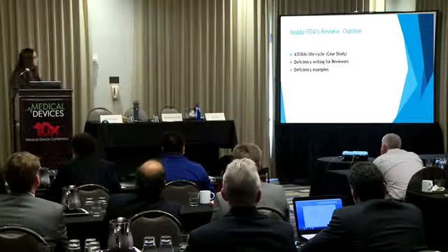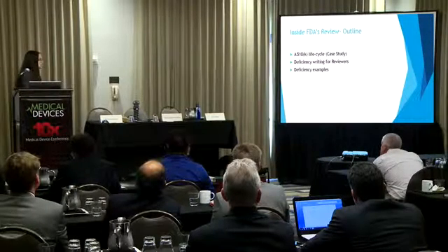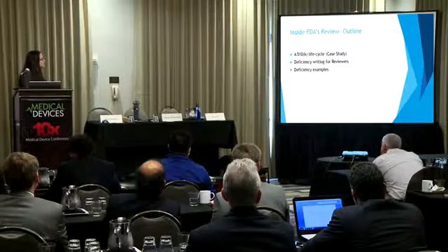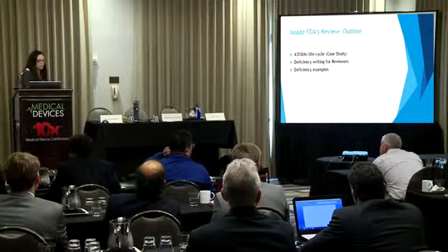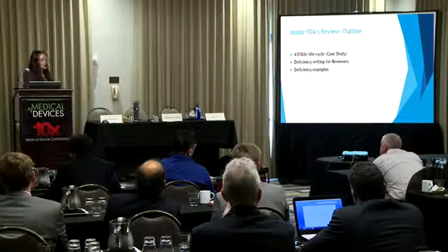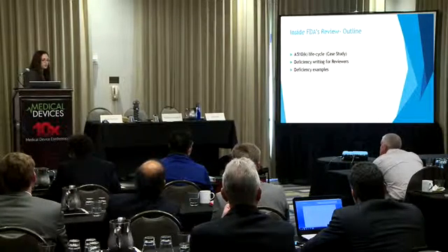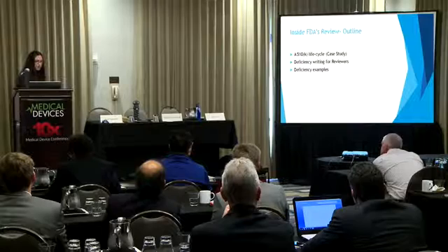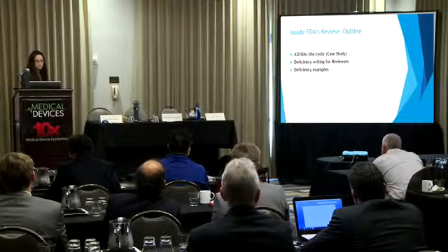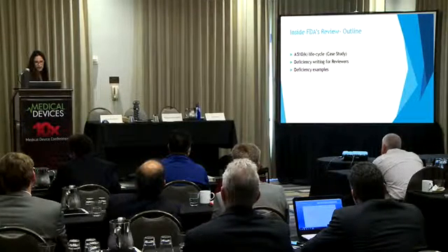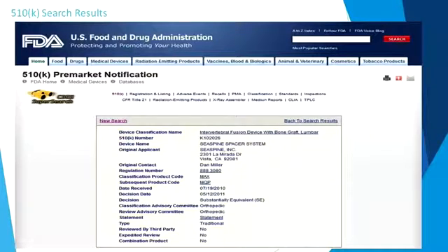So Rob had a great slide with the database. So this is the 510K database. I looked up this is for a client that was looking for something that had a nano coating. That was something they wanted. They had a nano metal coating and they wanted a predicate. So this popped up. I don't even think the name's on it. SeaSpine's the company. They're here in San Diego. You can see the registration number, or the regulation number and the classification number. So it's their 3-letter code, MAX.